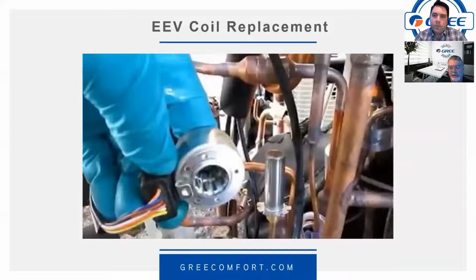If you've done the other checks, as you're going down the list, we're getting harder and harder. If you've done the other checks and you haven't fixed the problem yet, then you've got to keep going, and this is the direction to go. I've actually had several instances where a board was replaced and it turned out an EEV was shorted, and it ended up causing damage to the new control board. So if you do have a reason to replace a control board, inspect that control board too, just to make sure, okay, does it have a burnt spot, and if it does, trace that circuit down just to make sure you don't need to look at other components. Yep. Yeah, really good point.